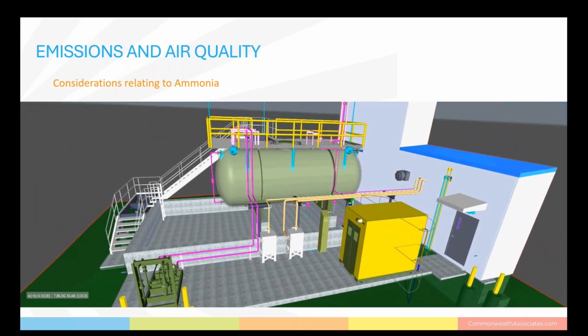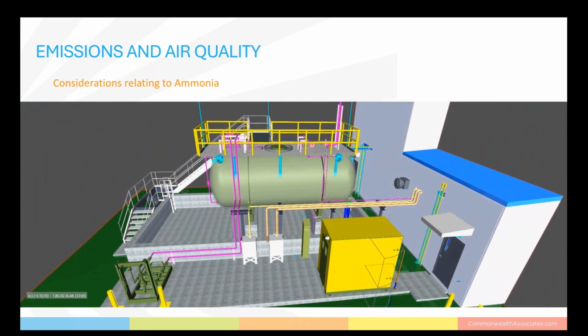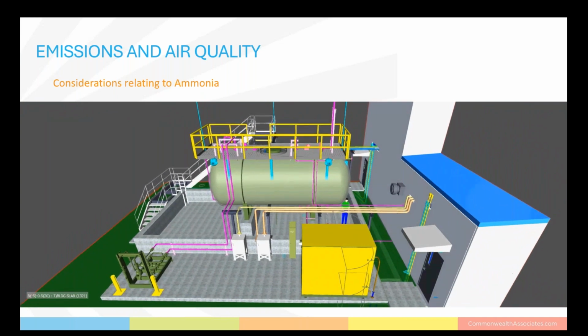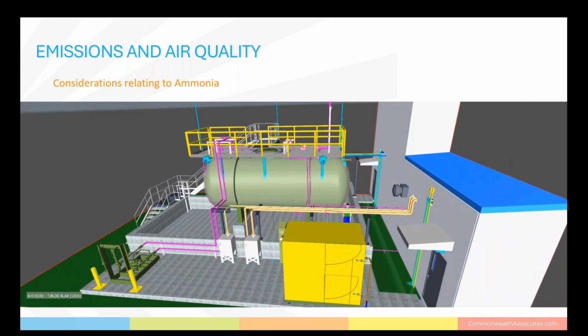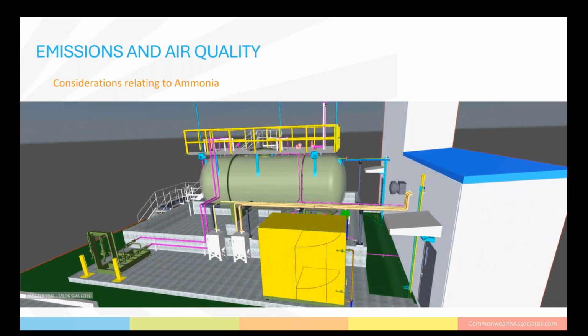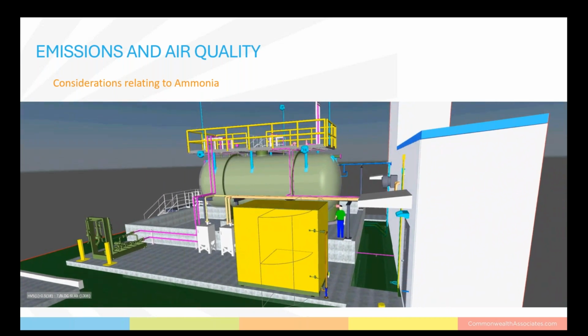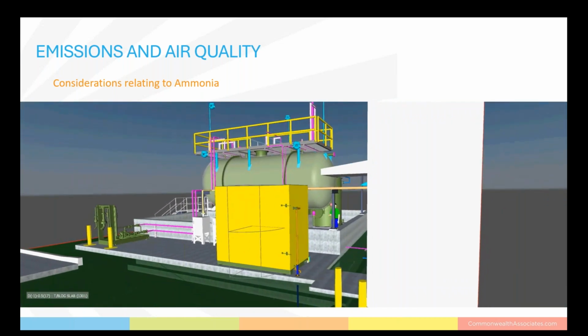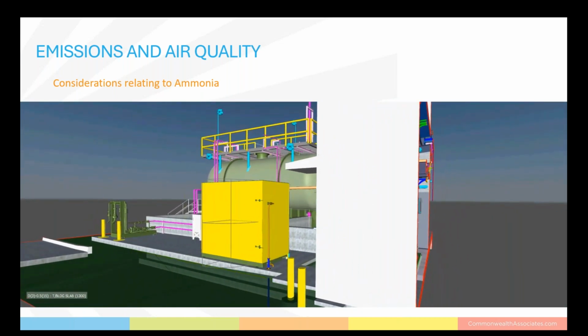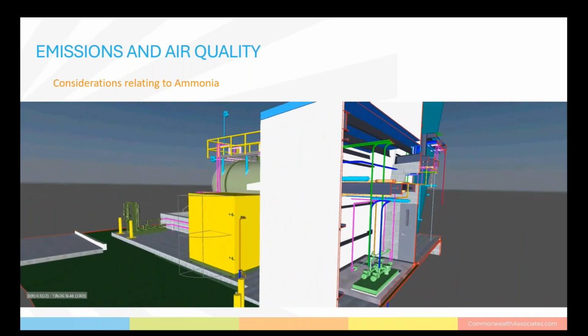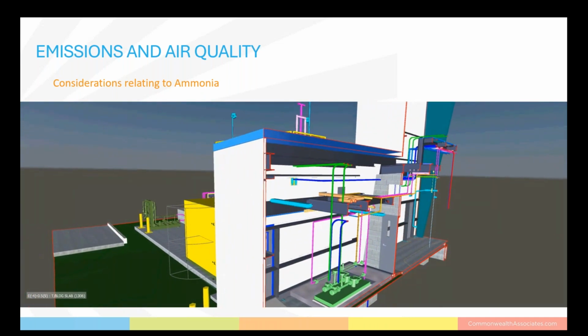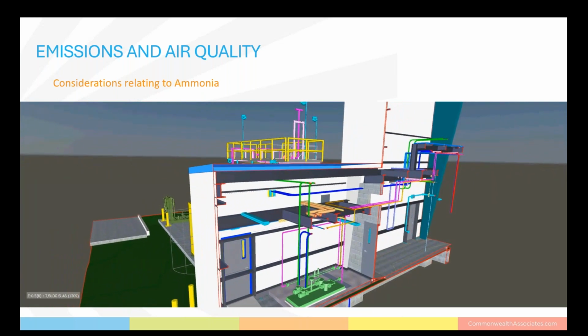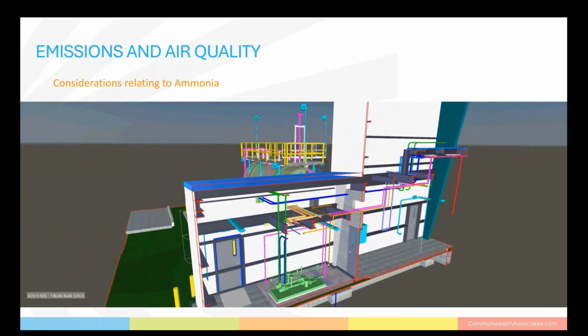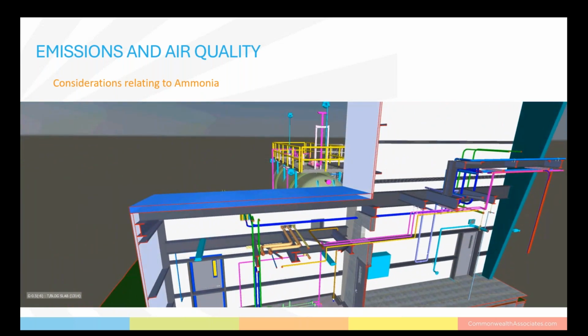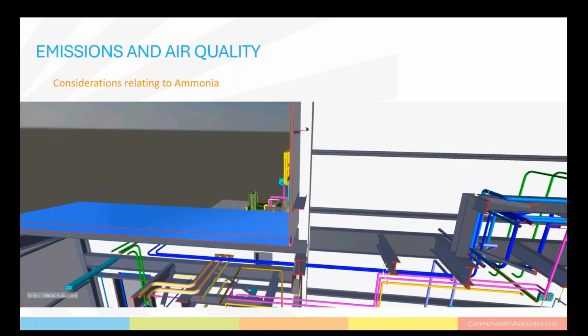It's also good practice to install bollards to protect the skid from accidental truck contact. Ammonia is hazardous, so there needs to be a safety shower shown here in yellow. The ammonia tanks are typically horizontal style and elevated to allow access to the valving off the bottom. The elevation also helps with head for pump suction. In this case, the forwarding pump sits just inside the building, shown in green, to protect it from the environment.